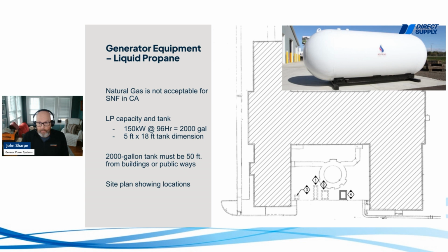In this particular project we worked on, this was a little courtyard, and we had an LP solution, a liquefied propane solution. We were able to put a tank in here because they were only putting in a 24-hour tank. But if you want to put in a 96-hour tank, once you break the threshold of 2,000 gallons, it requires you to be 50 feet away from everything. As it is, if you're looking at anything over about a 250 gallon tank, you've got to be 20 feet away from everything.